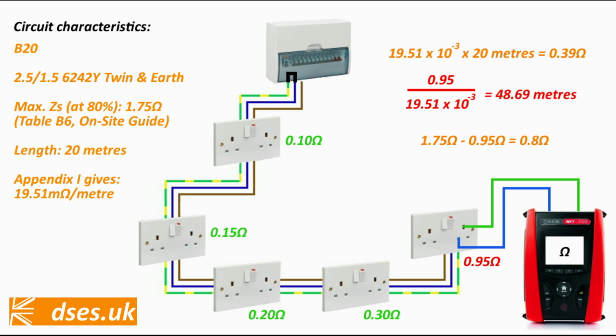It's not enough to know the earth fault loop path passes on an ohmmeter. You also need to be sure the number you're getting is right for the circuit length, and that the neutral is also sound. So after your R1 plus R2, you need an Rn plus R2, which should give you the same result, thus verifying all the live wires are sound in their connections. In this example, Rn plus R2 gives us a completely different figure to the 0.95 ohm recorded for R1 plus R2, potentially indicating the neutral and CPC are good, but there is a loose connection on the line, and that the 0.95 ohm figure we recorded isn't the glittery pass we thought it was.